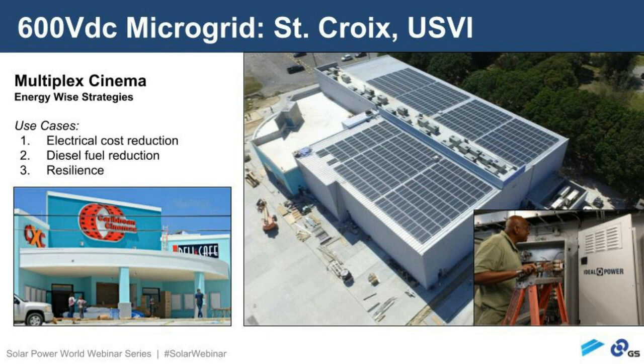The big difference here between this one and the previous two is that this is where a true energy management system comes into play and has to be developed. Multi-port inverters, battery BMS, and diesel generator controllers all have tightly defined operating parameters, but they are essentially independent devices, and they have to be managed by a site controller.